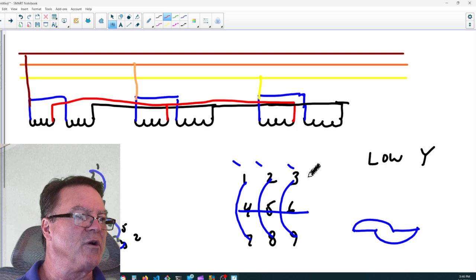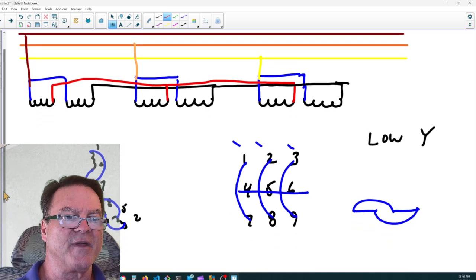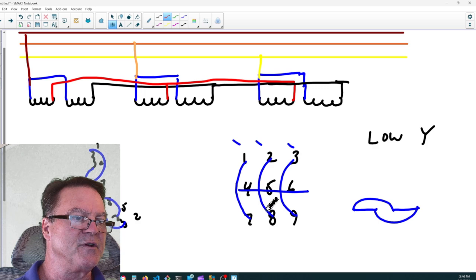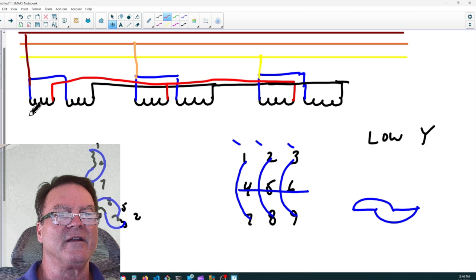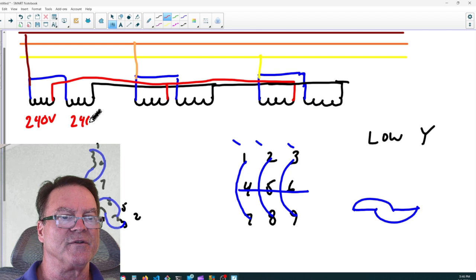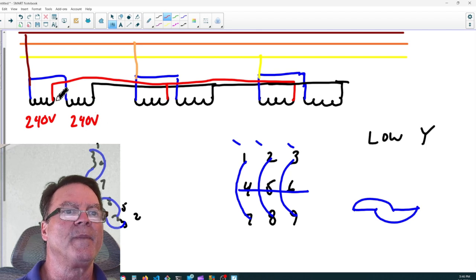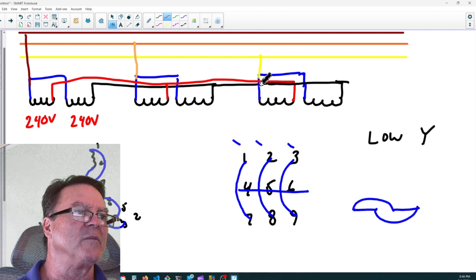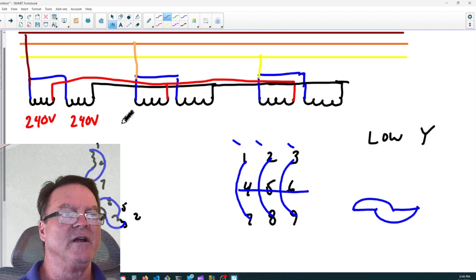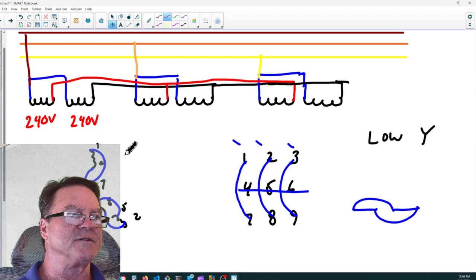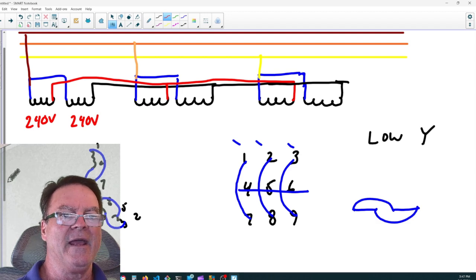When we go to low voltage, we'll go in parallel. So it ends up that 1 goes to 7, 2 goes to 8, 3 goes to 9, 4, 5, and 6 tie together. And again, if this is good for 240 volts, and this is good for 240 volts, well, anyway, they're tying together, and you're not putting 480 volts across them. You're only putting 240 volts across it. So it doesn't end up putting double the voltage on it.